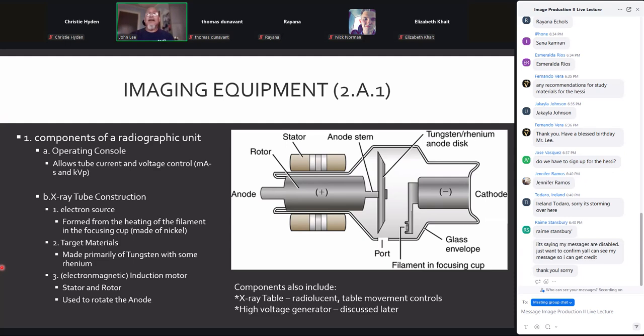Focusing cup is primarily made of nickel. We'll hit some of the highlights here on this. Your target material, primarily tungsten, a little bit of rhenium, but the tungsten has a high atomic number, gives us a greater amount of higher energy X-ray when we energize the system. The induction motor is driven by electromagnetics, and the two components are the stator and the rotor. X-ray tables, radiolucent. Be familiar with table movement and controls and how they're labeled. And then the high voltage generator we'll get into in just a little bit.